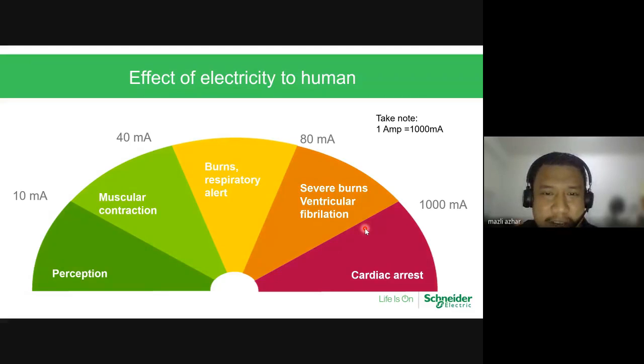Okay, it is a requirement that every water heater company put an ELCB or RCCB integrated inside the water heater. But take note that some people have the idea that, oh, I do have a water heater with ELCB inside, so I don't need to add another 10 milliamp protection when I use a water heater. It's a wrong impression, whereby you need to put another 10 milliamp RCD at the final distribution panel to protect the whole system. Because the ELCB at the water heater itself is to detect leakage at the water heater only.